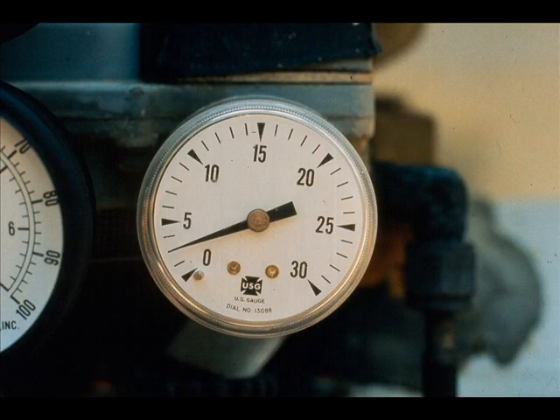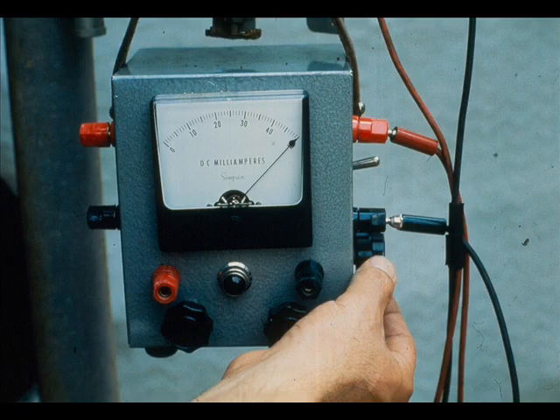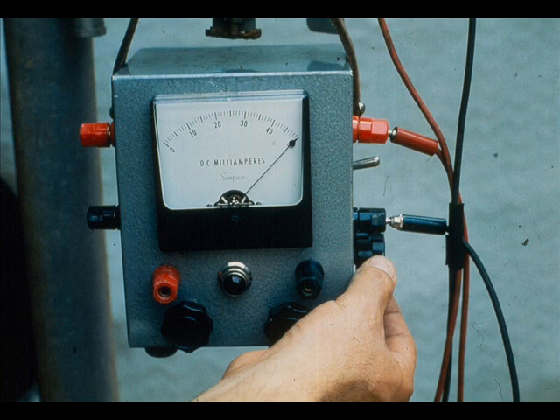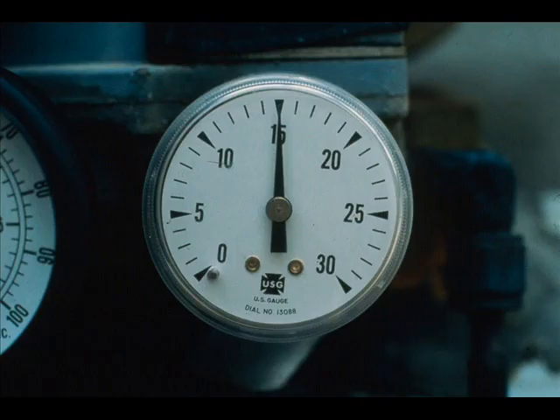The transducer output should be 3 PSIG. Using the coarse and fine adjustments, set the output to 50 milliamps. The transducer output should be 15 PSIG.